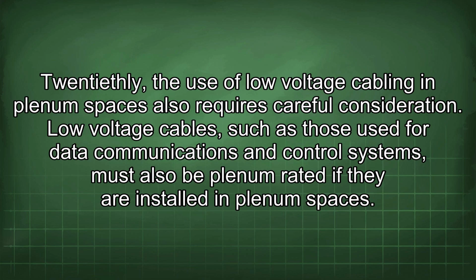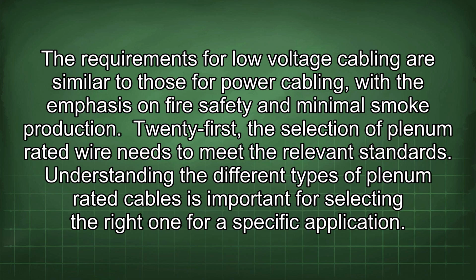20thly, the use of low-voltage cabling in Plenum spaces also requires careful consideration. Low-voltage cables, such as those used for data communications and control systems, must also be Plenum-rated if they are installed in Plenum spaces. The requirements for low-voltage cabling are similar to those for power cabling, with the emphasis on fire safety and minimal smoke production.